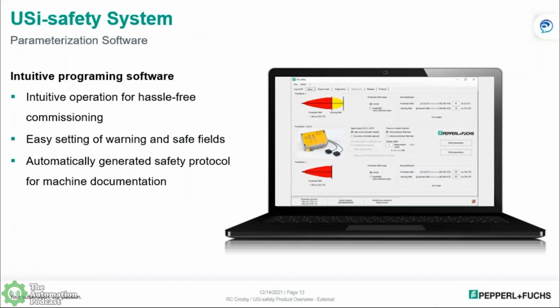So with some of our other software, if you're familiar with us, you can set up a bunch of sensors at one time and just hit send, and really it takes you as long to plug in the M12 as it is to click send and save to the sensor. In this case, you have to do it one by one and go through the full steps each and every time. That's a part of the safety certification, so we can't really skirt that. So, yeah, it's a little bit time consuming there, but in the end, that's how we achieve the safety rating.